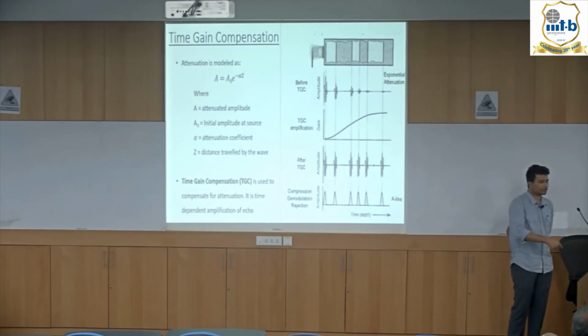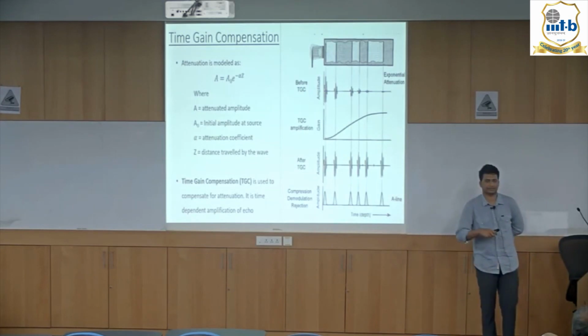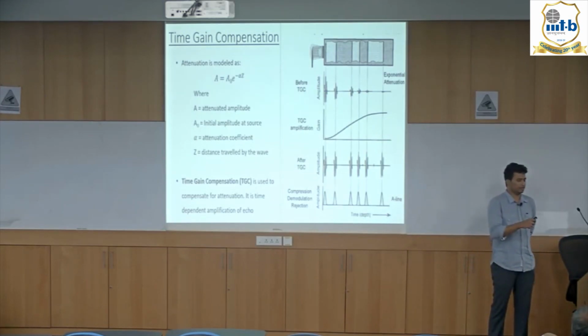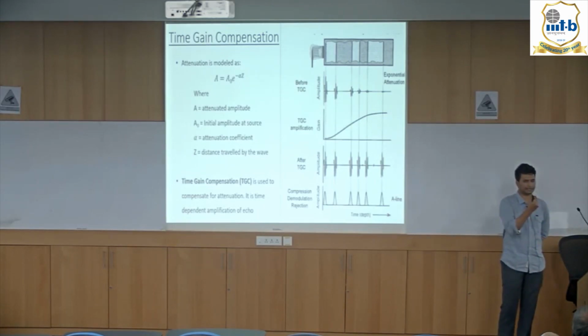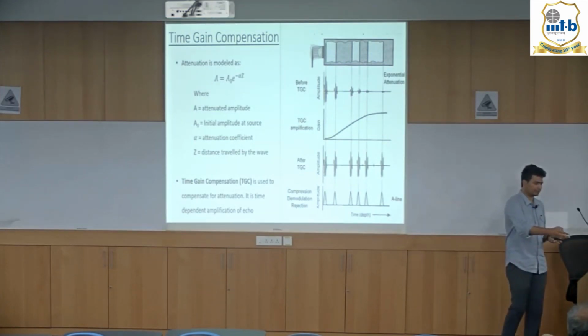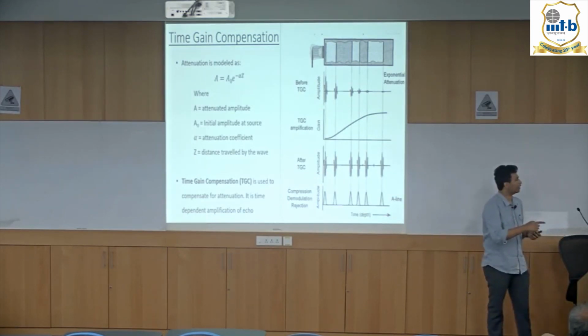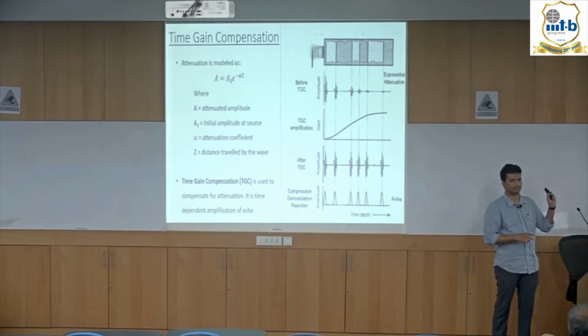So a technique called time gain compensation is used, where the received electric signals corresponding to the echo are amplified in time. It's a time variable amplifier which they use to implement TGC. After TGC, you can see that the echo amplitudes almost have the same peak to peak value.